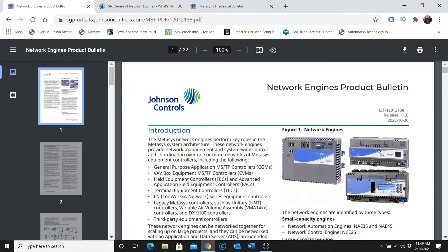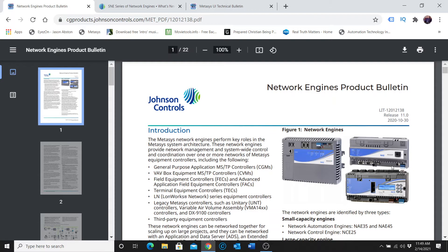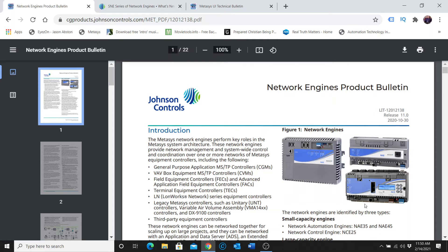Actually, at the time that I'm making this video, the smaller frames are strongly encouraged, or I would strongly encourage you guys to not install any of those if you intend on upgrading your Metasys software. These are not able to be updated past 9.08 version of Metasys. I know that there are some sites that are starting to see a lot newer versions of Metasys being used, so these devices cannot be updated to a lot of newer versions. I know that the version that we're at, we have several that cannot go to it currently and we are looking at upgrading even further.